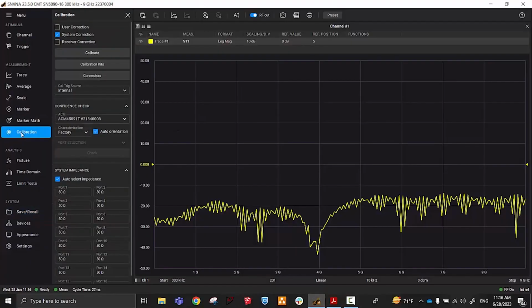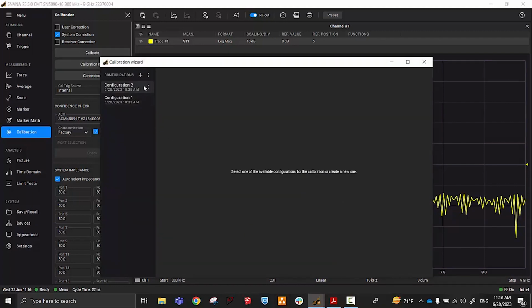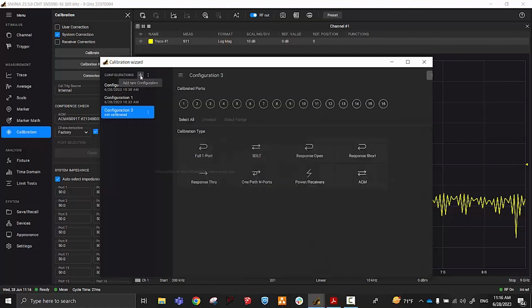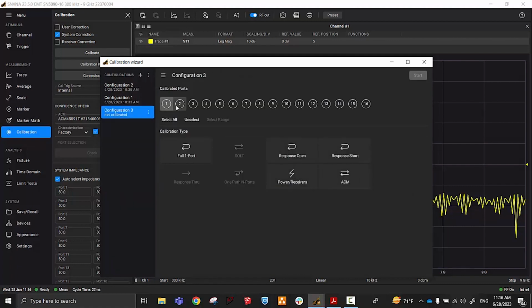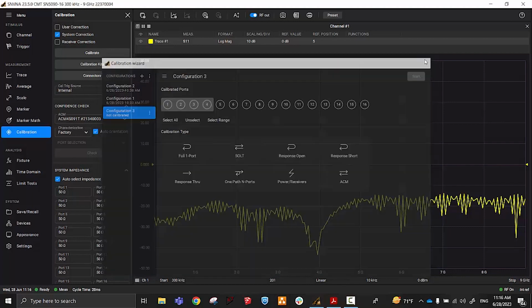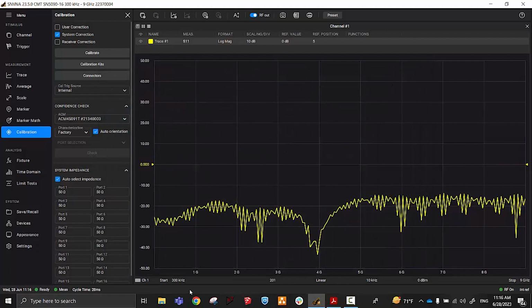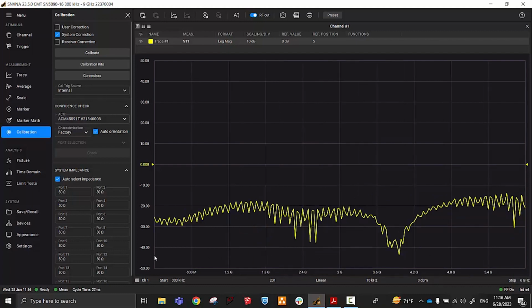So I'll go to the calibration menu. I will say calibrate. And I'm going to add a configuration. And I'll select ports 1, 2, 3, and 4. Oh, actually, before I do this, let me back up and change the range. The splitter is only good to 6 gigahertz, so we'll make it stop there, 6 gigahertz. And the starting 300 kilohertz is fine. We can also change the number of points to 1601. So it's important to get all this set up before you do your calibration.